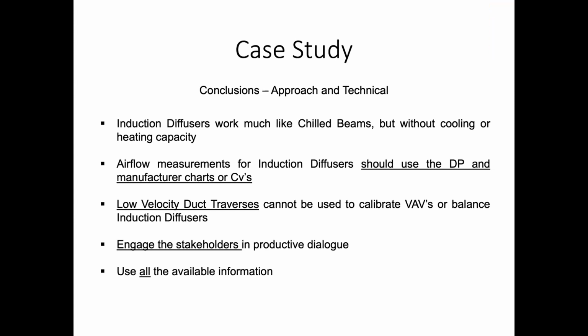Okay, thank you. And I'm looking at Blake now. Typical DP issues seen with DP chilled beams are with installations, for example, leakage at connections, or disregard for leaving valve pressure drop. And they put an example: you can get 0.7 inches WC at the device if the valve is charging at 0.5 inches WC. Did this come into play with your experience at all?